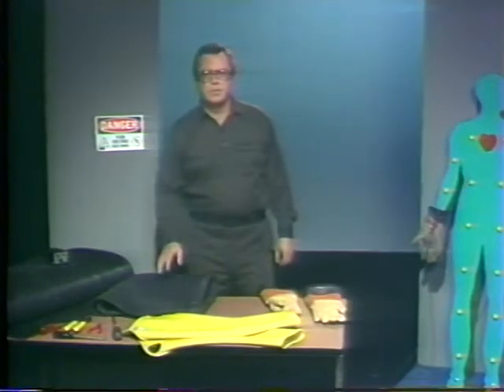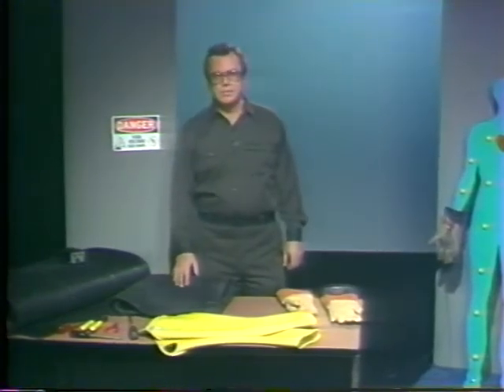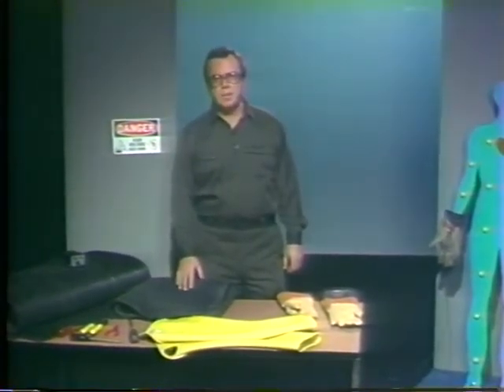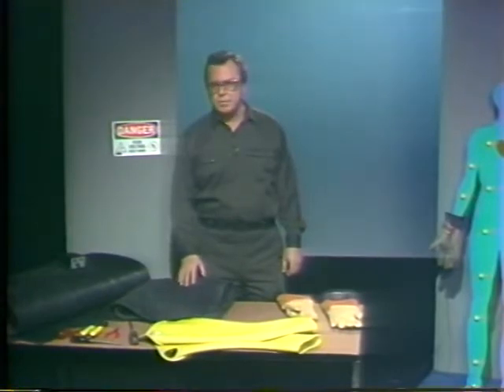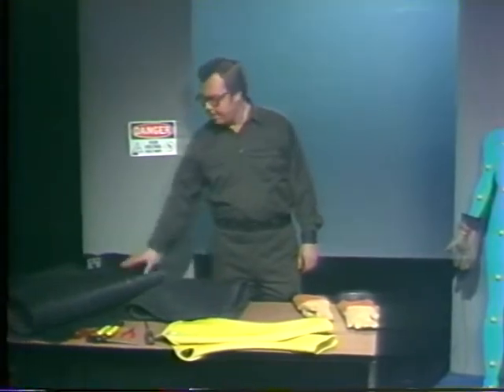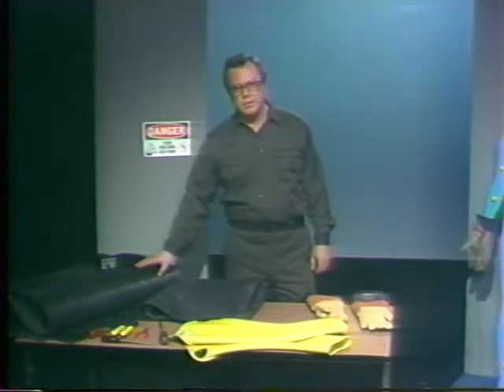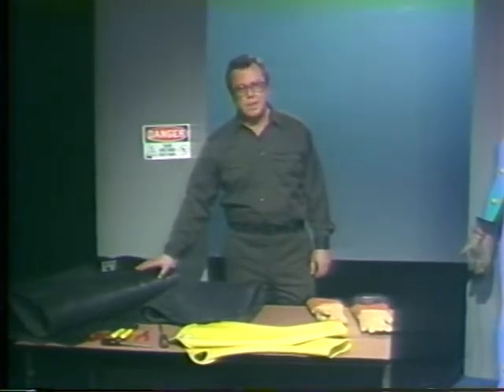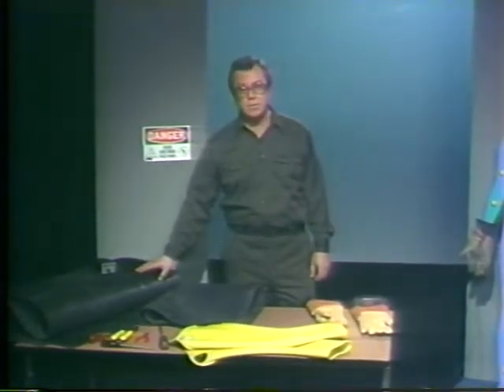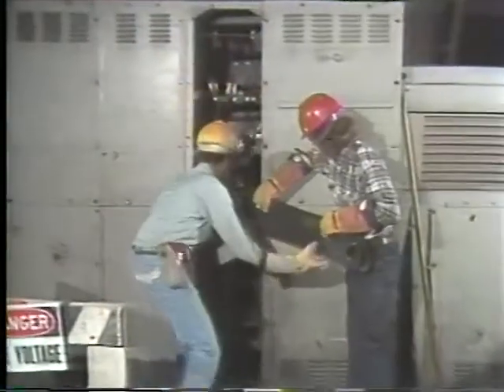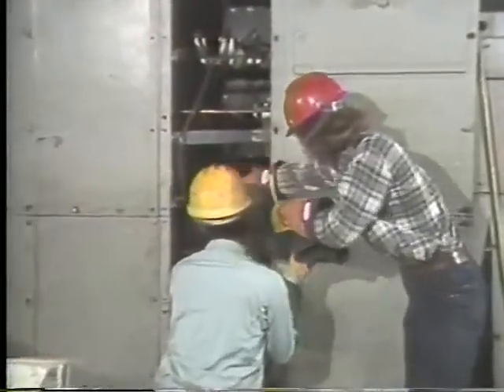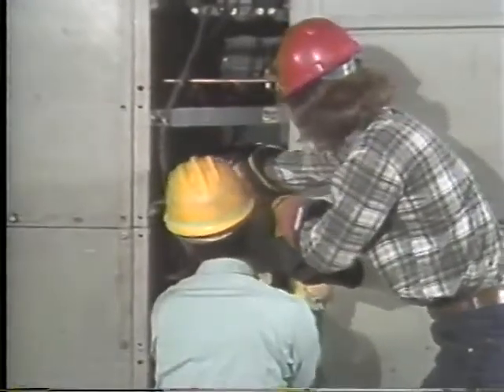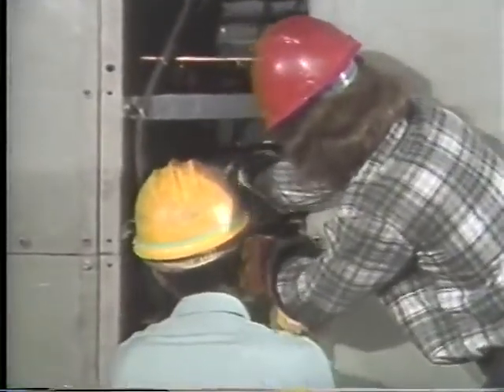Rubber blankets and floor mats are used in many situations. Blankets are used to cover up energized conductors when you have to work on something nearby. Floor mats keep you insulated from ground, so if you do contact something hot, the current can't flow through your body to ground. Here's a typical application for rubber blankets. Covering the energized main buses in a breaker panel before working on a de-energized breaker. Once the hot buses are covered, it's safer to reach into the breaker load terminals.